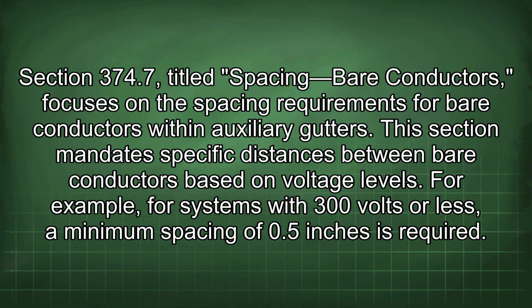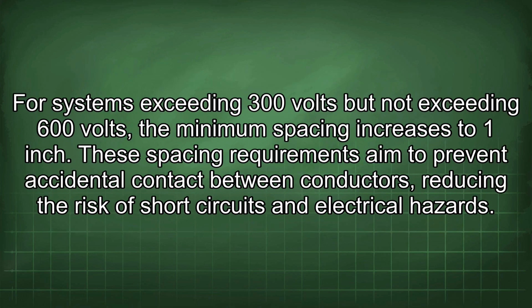Section 374.7, titled Spacing of Bare Conductors, focuses on the spacing requirements for bare conductors within auxiliary gutters. This section mandates specific distances between bare conductors based on voltage levels. For example, for systems with 300 volts or less, a minimum spacing of 0.5 inches is required. For systems exceeding 300 volts but not exceeding 600 volts, the minimum spacing increases to 1 inch. These spacing requirements aim to prevent accidental contact between conductors, reducing the risk of short circuits and electrical hazard.